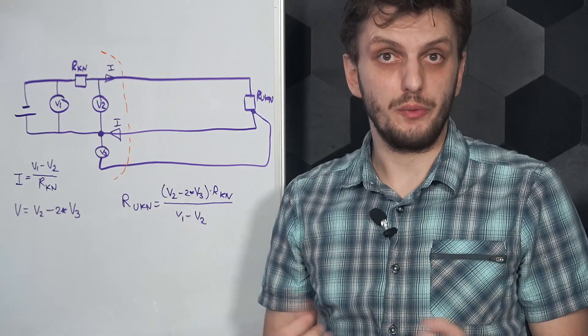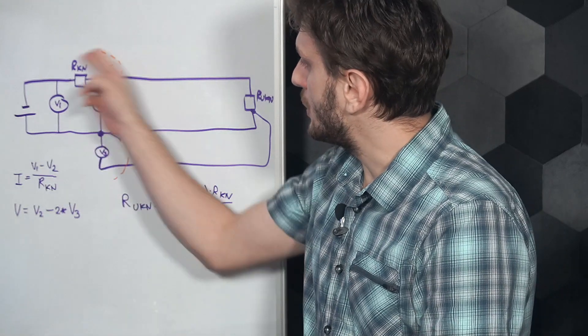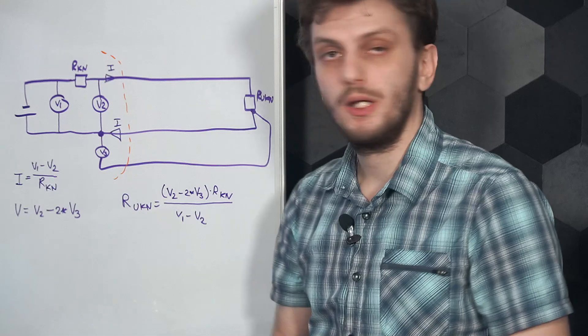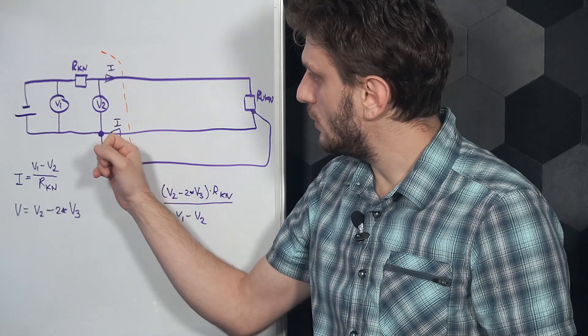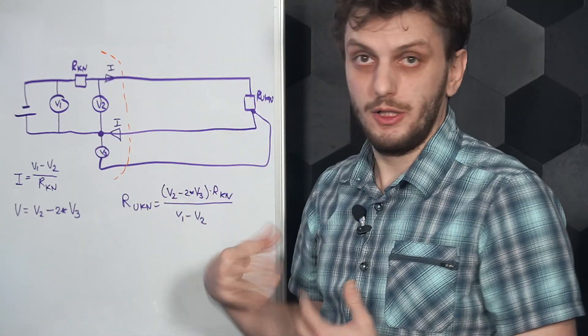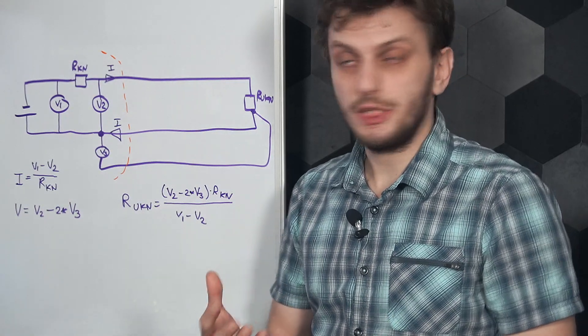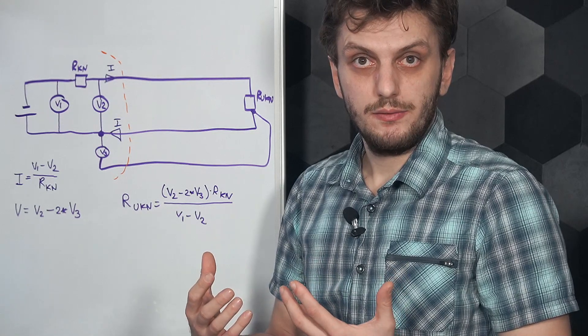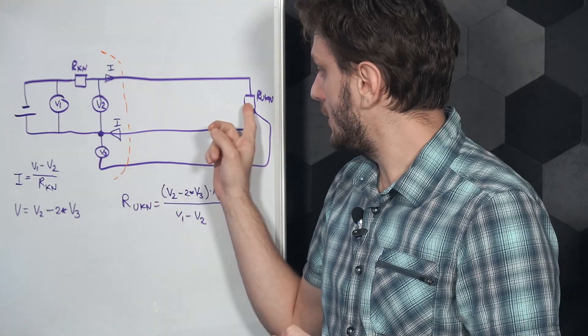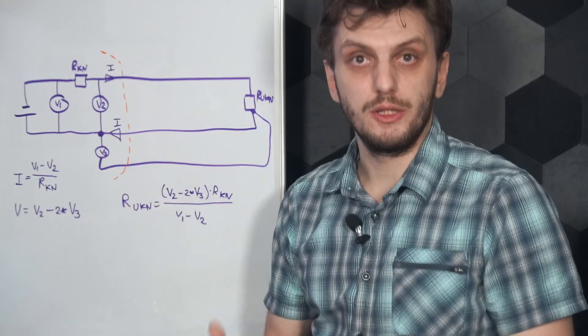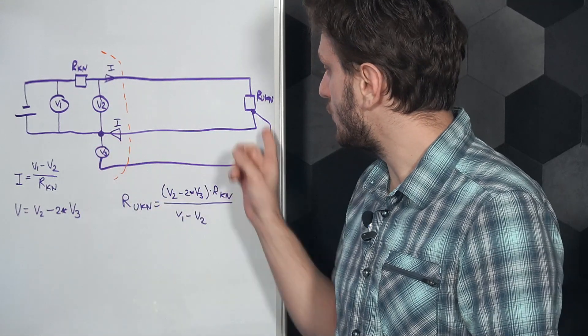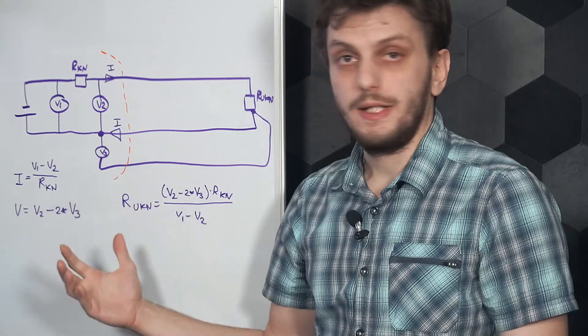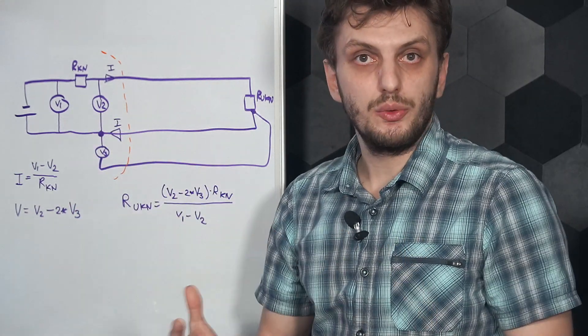The other way to perform a 3-wire measurement looks like this: as before, we inject a current and measure it using our first two voltmeters and our known resistor. This current travels through one line, through the unknown resistor, and back through the other. The voltage measured by our second voltmeter equals the voltage drop on our unknown resistor plus the voltage drop on our two current-feeding lines. If we consider the two lines to be identical, the value we're after is the voltage drop on the unknown resistor minus two times the voltage drop on one line. We use our third voltmeter to measure the voltage drop on one of the lines, multiply by two, and subtract it from our total voltage measurement.